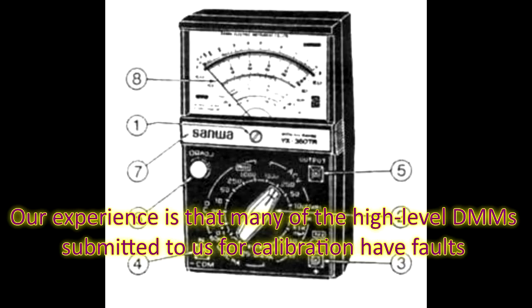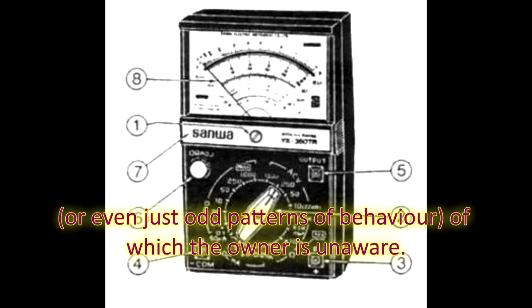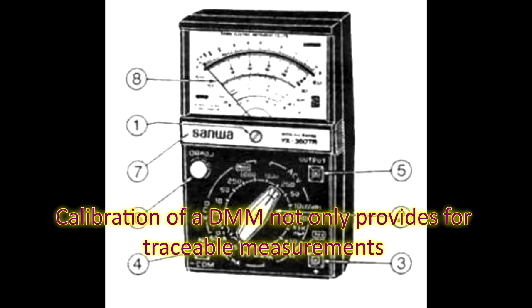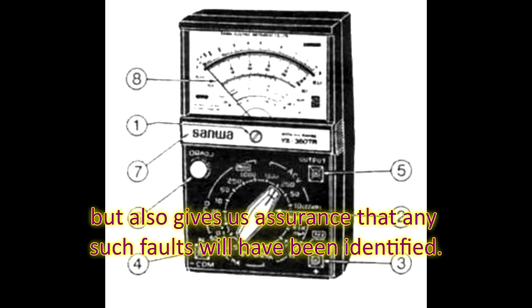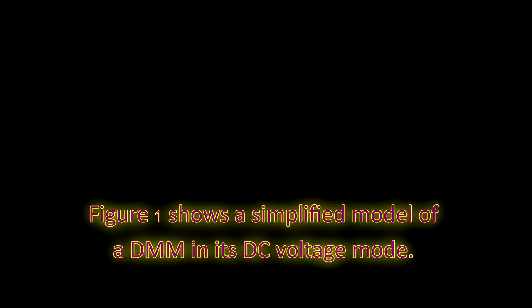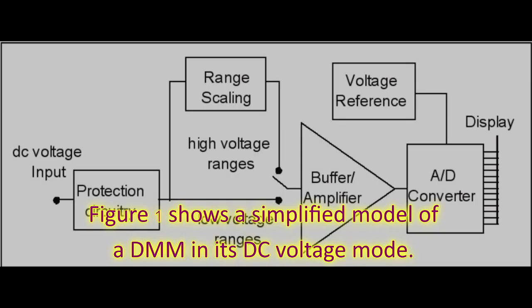Our experience is that many of the high-level DMMs submitted for calibration have faults or even just odd patterns of behavior of which the owner is unaware. Calibration of a DMM not only provides traceable measurement but also gives us assurance that any such fault will have been identified. Figure 1 shows a simplified model of a DMM in its DC voltage mode.